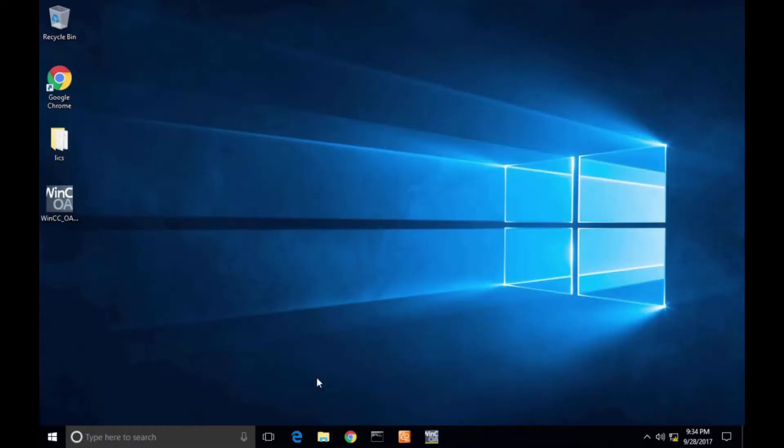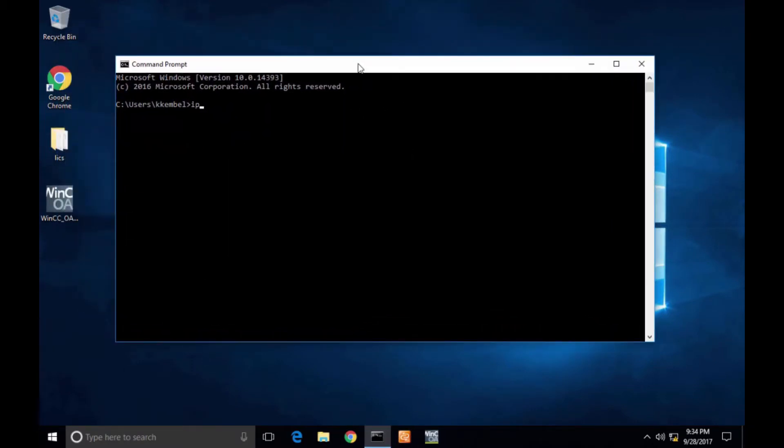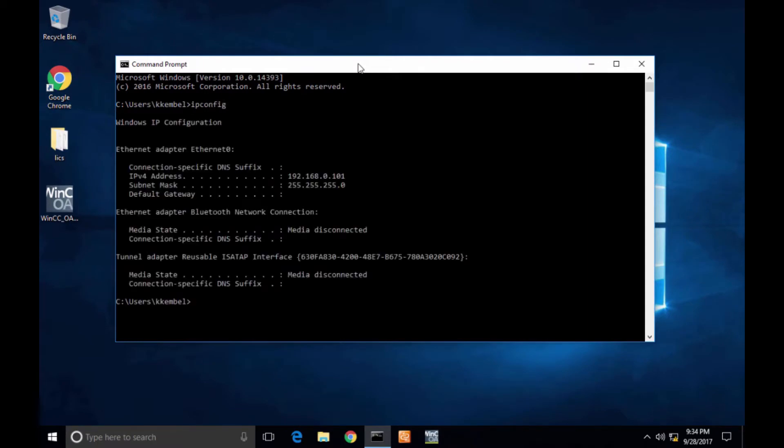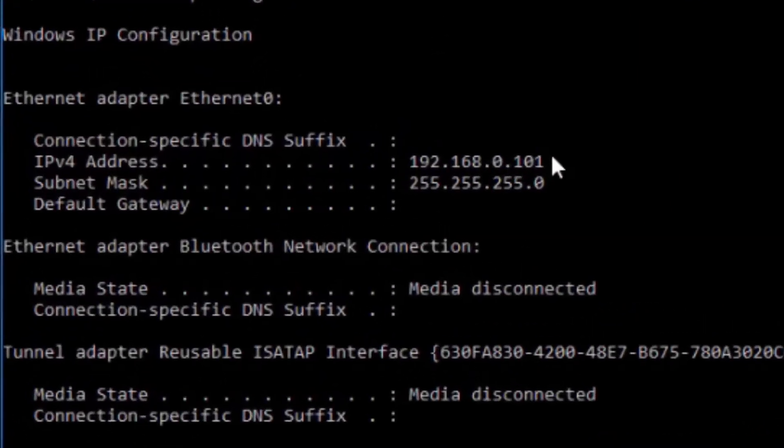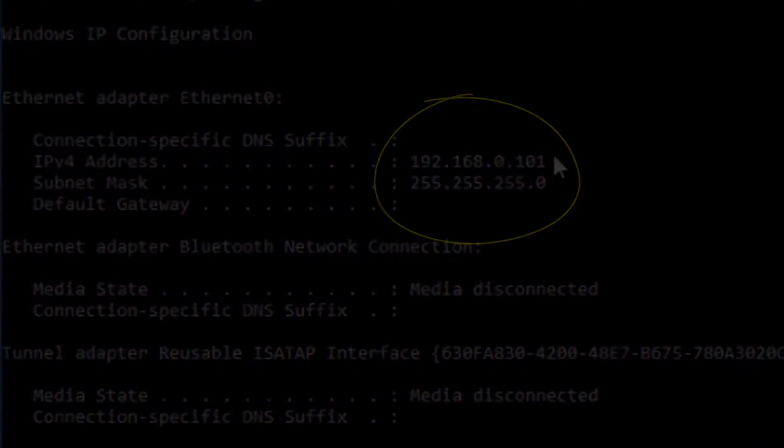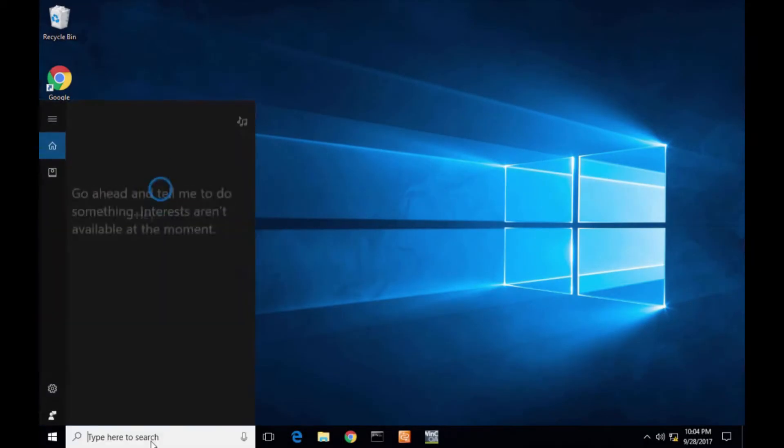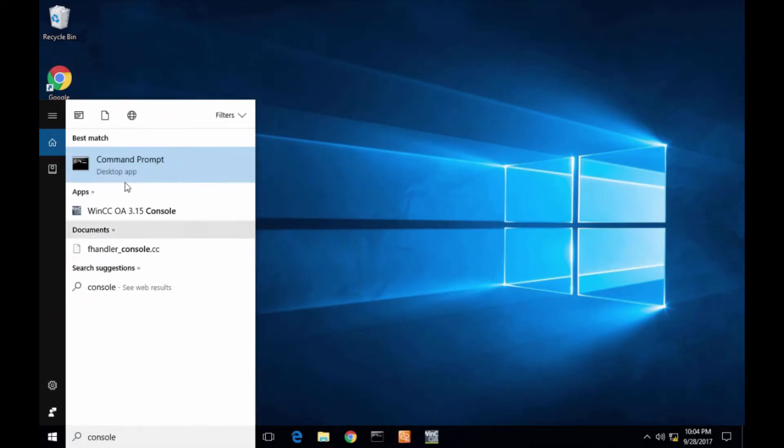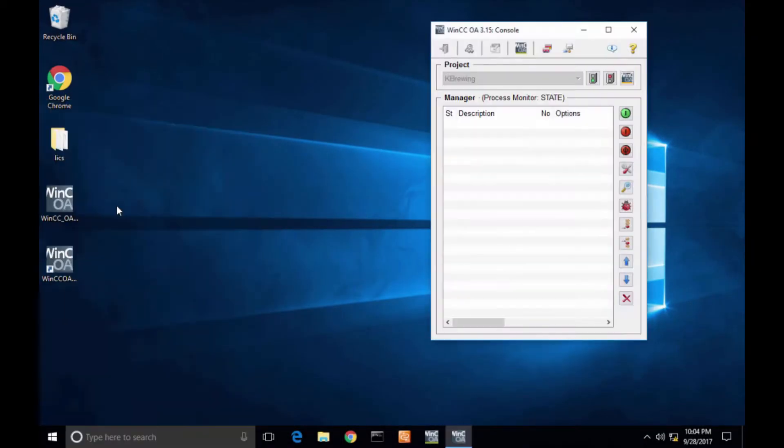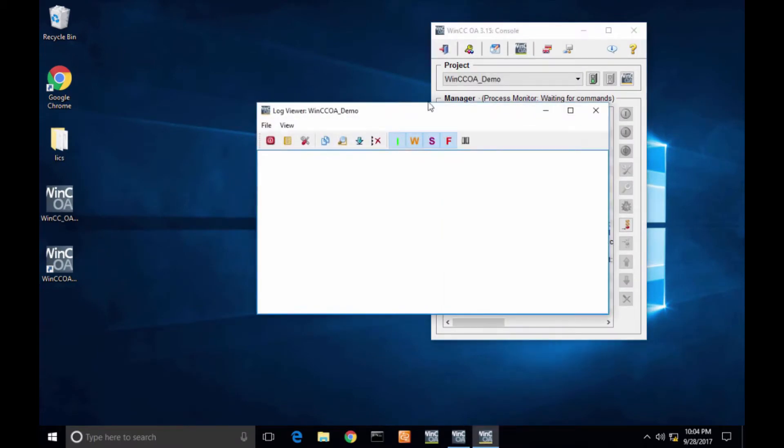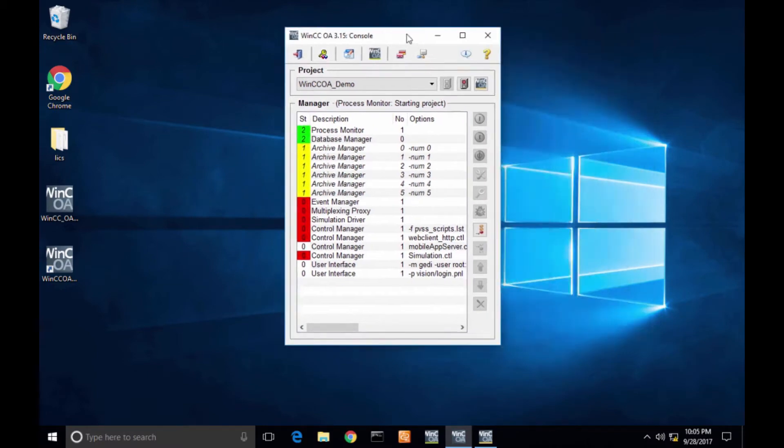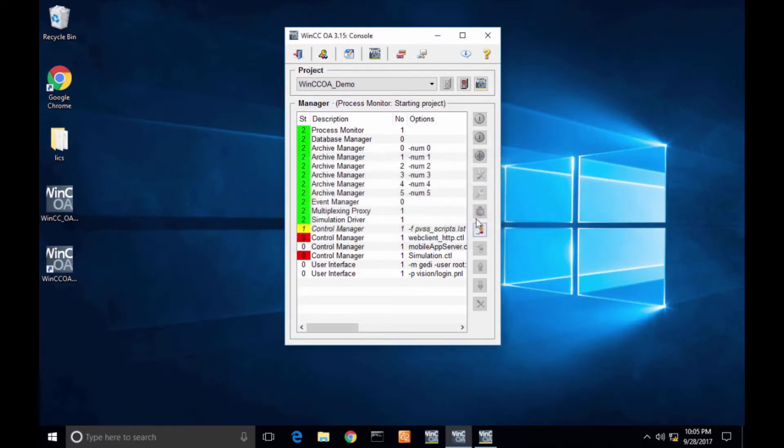So James, I'm going to do two things. One, I'm going to set up the server and start an application. And then the second one's going to be configuring the actual Thin Client. So the first thing that I need to do is log into the WinCC OA server and open a command line prompt and type in ipconfig. All I'm doing here is getting the IP address of the server. After I do that, the next thing that I want to do is click the start menu. I'm going to find the WinCC OA console and I'm going to pick my project that I want to launch. I'm going to put that into runtime to make sure that I have an application up and running. And that is exactly what I'm going to show on the Thin Client.